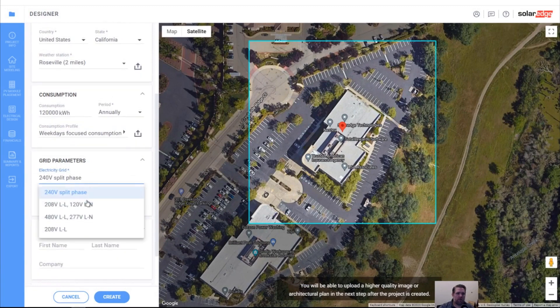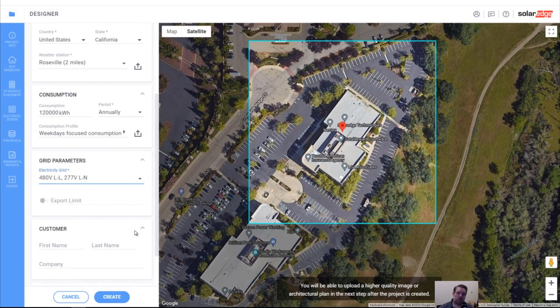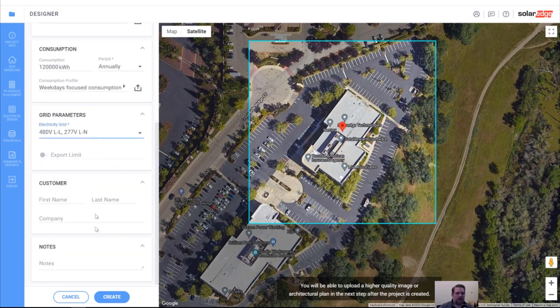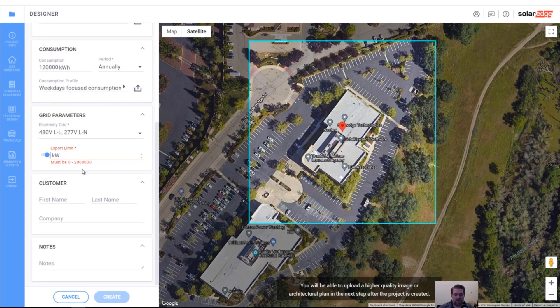The grid parameters are going to be defined as what is available at the main service panel. This is a 480-volt building, so I'm going to pick 480 volts. We can type in notes and define the customer, and we can even define an export limit — maybe you're not allowed to export more than 15 kilowatts. For a commercial system we might say we can't export more than 200 kilowatts, meaning if we load the roof with more than 200 kilowatts it will never export more than that.